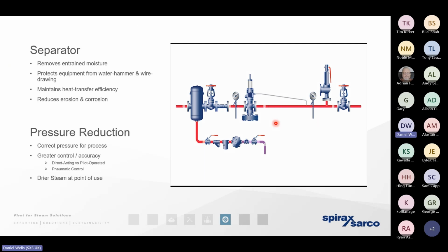Drying the steam. As we've mentioned, wet steam is more likely to create a problem with erosion of control valves or of flow meters, for example. But it also means if we've got very, very wet steam, there's less energy present within the steam and therefore the boiler has to work harder. So ensuring that those separators are installed correctly is vitally important. They're quite often engineered out of steam systems when it comes to looking for areas where we can save a few pounds on the installation, but they're vitally important when it comes to understanding where that inefficiency may exist.